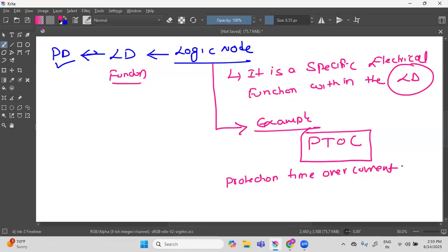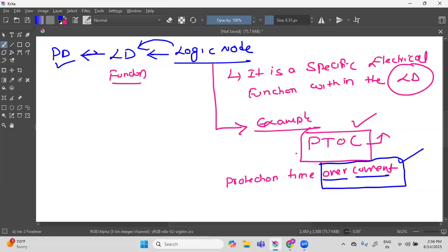For example, I told you if a branch falls on the wires, there is increase in current. Who will detect it first? It will be detected by PTOC. This specific function measures one parameter only - overcurrent. Now when overcurrent comes, this logic node will inform the logic device that the power issue is there.